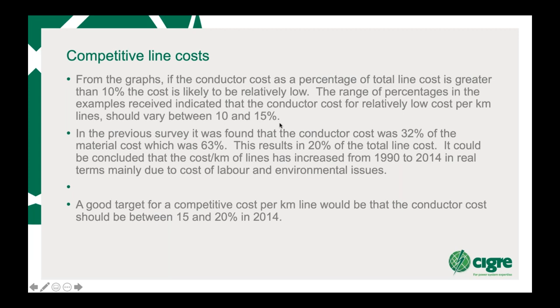So in the previous survey, it found conductor cost was around 32% of material cost, which was 63%. That results in 20% of the total line cost. So in other words, if your conductor was 20% in 1990, it was a good line. Now that's dropped to around between 10 and 15. So it could be concluded the cost per kilometer has increased from 1990 to 2014 in real terms. And this is really due to labor and environmental issues. So a good target for competitive costs would be that the conductor cost should be between 15 and 20%. And this brochure was written in 2014.